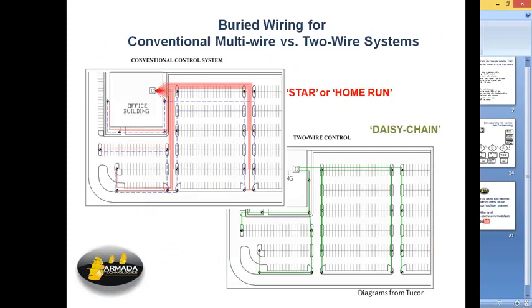do your troubleshooting. This diagram helps illustrate the difference between the wiring in these two systems, which makes a big difference in how your troubleshooting goes too. In a star home run, conventional multi-wire system, you've got a common running to every valve in the system, and you've got a single wire running to each of the valves independently, so they're fired with 24 volts. They're fanned out, kind of spread out, what I would call a star configuration, where all the wires home run.